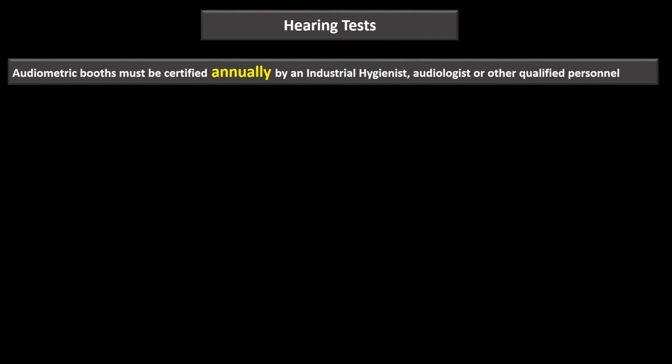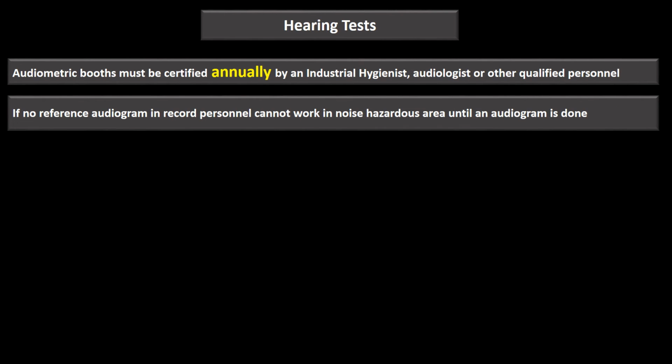Hearing test. So your audio booth needs to be certified annually by an industrial hygienist, an audiologist, or somebody qualified to calibrate it. If no reference audiogram is in the person's record, they cannot work in a noise hazardous area until that reference audiogram is done.